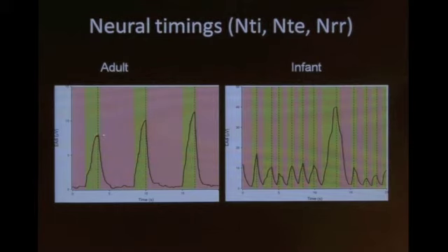So whether you put the cycling off right at the peak or at the green bar, which indicates a 70% cycling off, I believe there's very little difference between where this dashed line is and the green bar to the right. But you can see in the babies, for example, here, if you were to take this as the peak and it would cycle off the ventilator here, it would be too early. You actually need to prolong that a little bit. I'm going to show you in my next slide a little bit more. But clearly the difference in breathing pattern, here you have an upward rise and then a slower decline of the diaphragm activity on the expiratory phase.